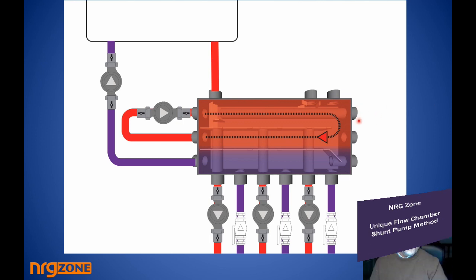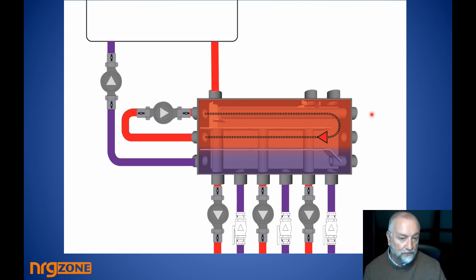So your actual high temperature might be in a low volume, and this shunt pump will overcome that scenario and allow every zone access to that higher temperature distributed among the lot. Your return water is not compromised. That's the difference. Even though you're shunting water and you're dissipating the heat from the solid fuel or whatever you want and from your gas boiler, your return water comes back from the returns and is not mixed with the shunt water. I don't know of any other scenario where this system works so well. It's a very unique and an extremely useful solution in particular jobs. We've used it many times with really great effect.